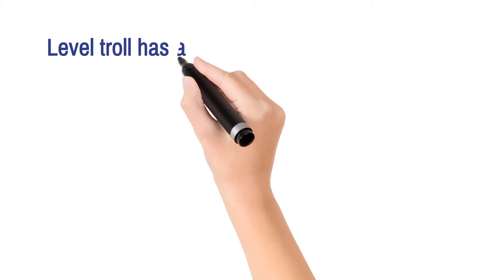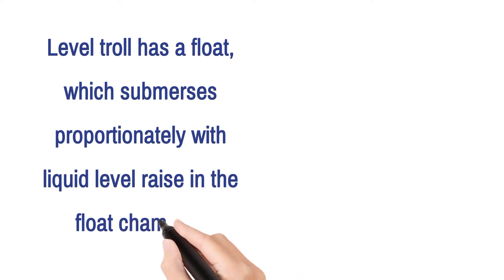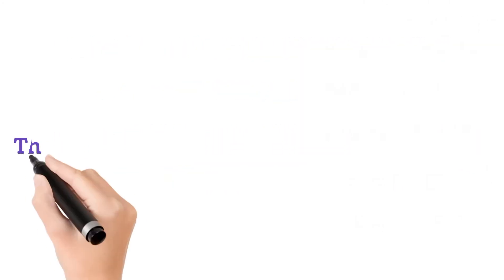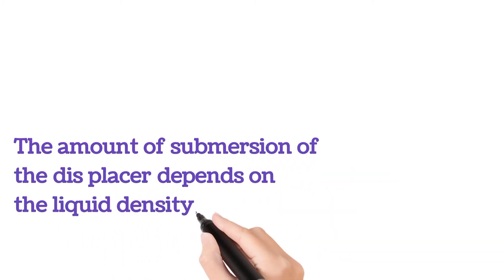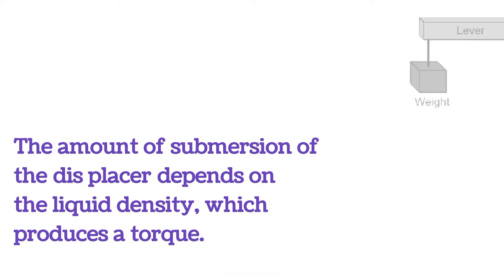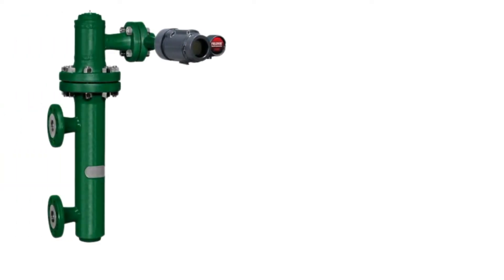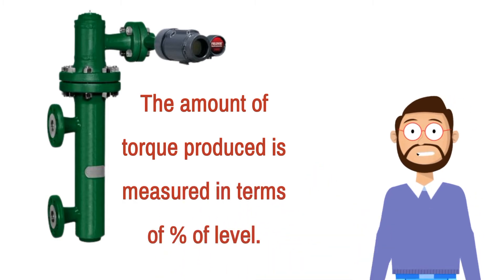Level troll has a float. This float submerges in the float chamber proportionally with the rise in liquid level. The amount of submersion of the displacer depends on the liquid density. Torque is produced due to sinking, and the amount of torque produced is measured in terms of percentage of level.